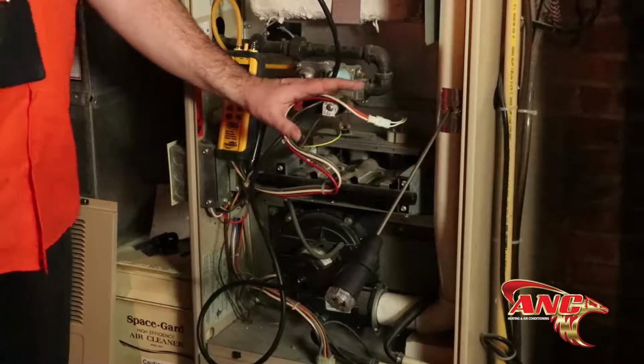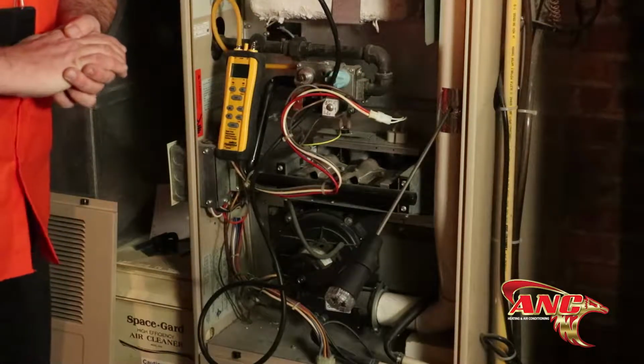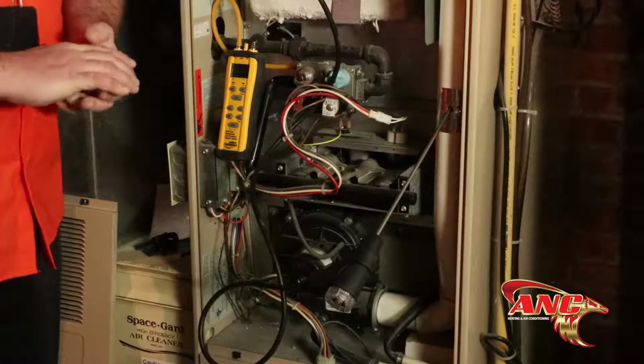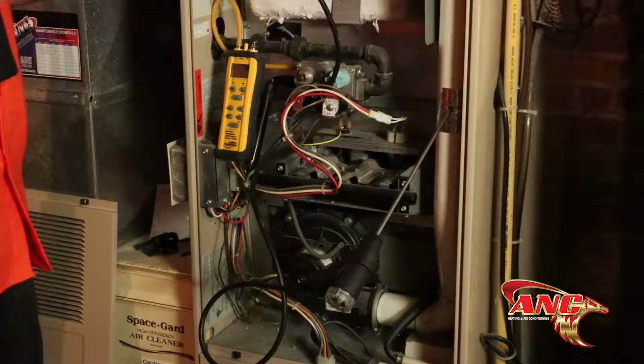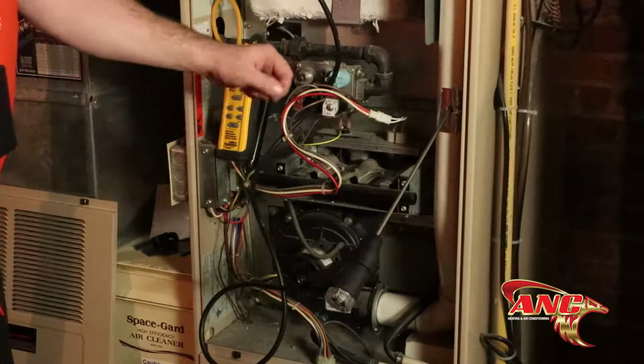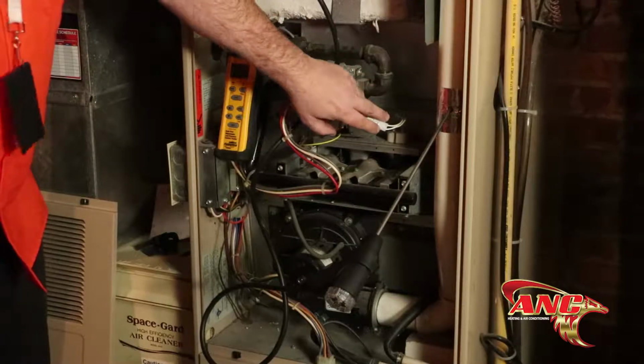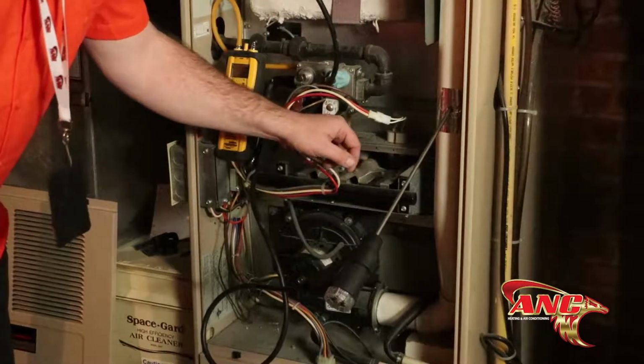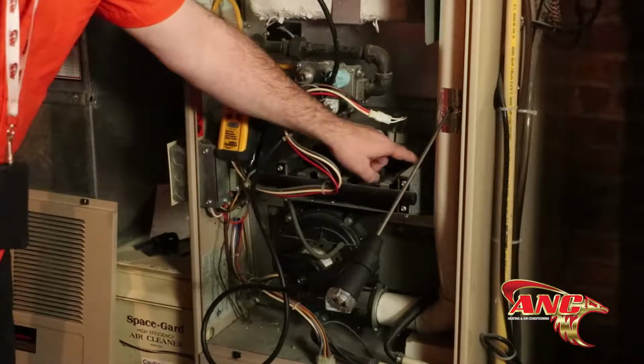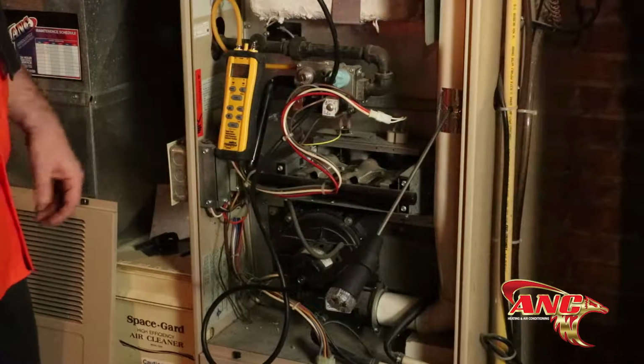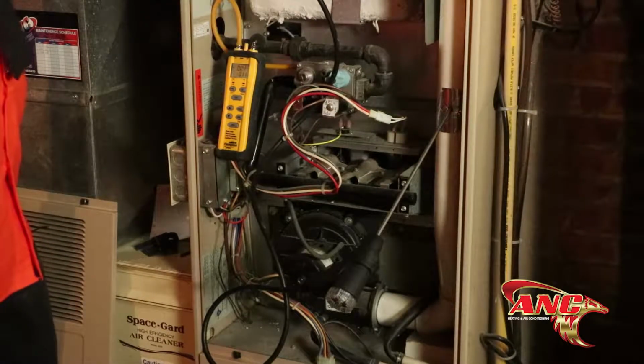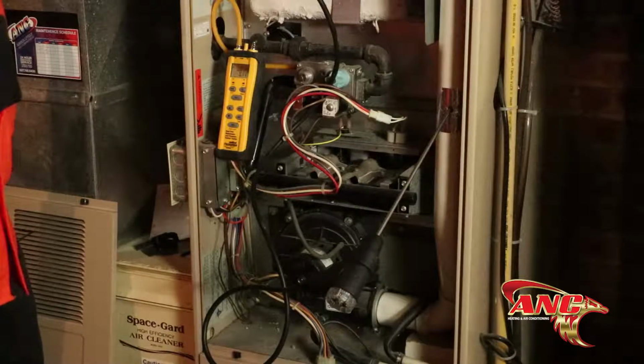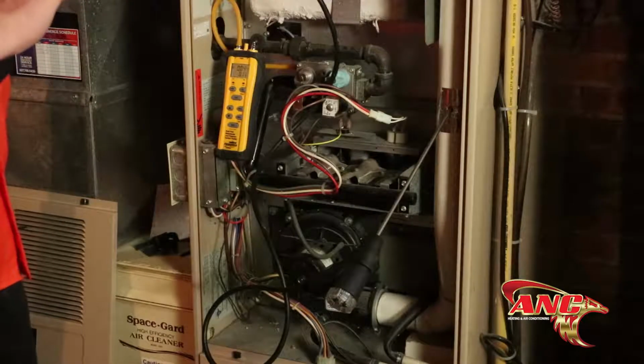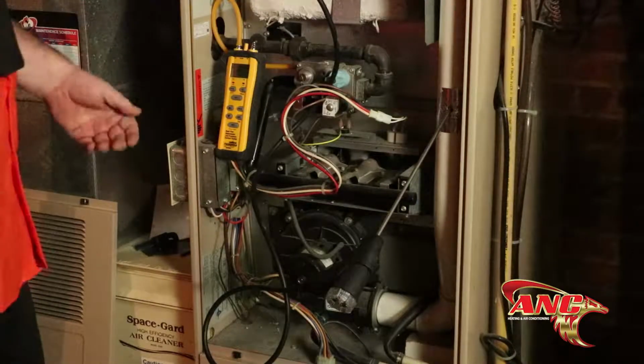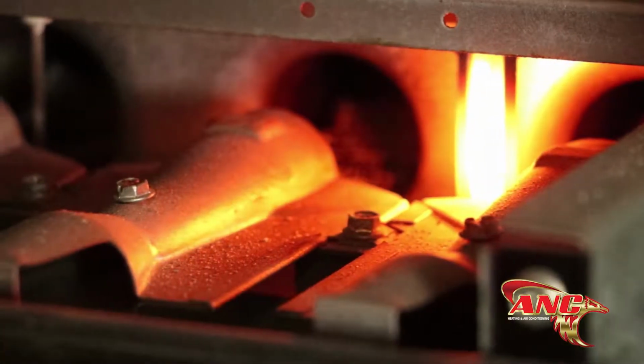There are safety devices to prevent anything bad happening, but over time, those things are not as reliable. Sometimes when I see flame rollouts, I'll see actually some wear on the wires. I'll see some wear on the metal right here. And a rollout usually indicates there's an issue with the heat exchanger. Could be a drain problem too. But all right, let's fire up and see what happens.